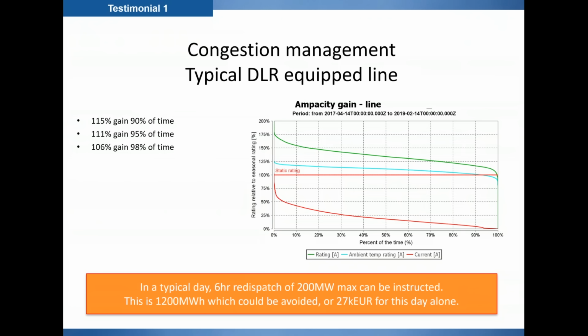Totality of the year. Now, if you translate that into monetary value, into euros and cents, using the same example as before, in a typical congested day, you would have typically 6 hours of redispatch hours. That would allow you to avoid 1200 megawatt hours of redispatching at the same value as what I've shown before. That would save you 27,000 euros per day on one congested day alone. So knowing that a typical DLR deployment on a line, depending on the technology you want to use, costs typically a few €100,000 per line, you would have recouped your investment in weeks. So we're talking about very quick return on investments here.